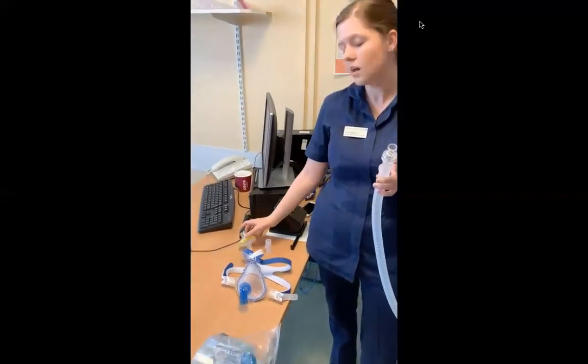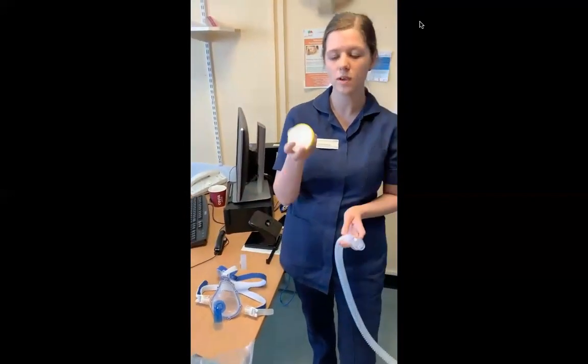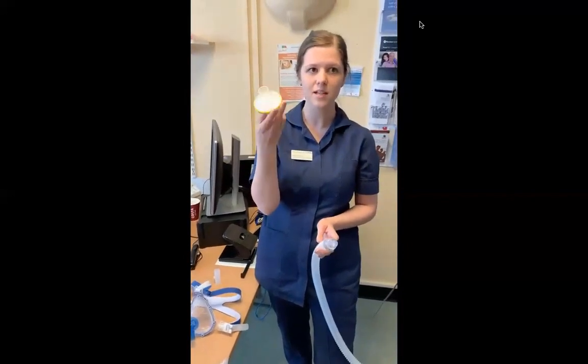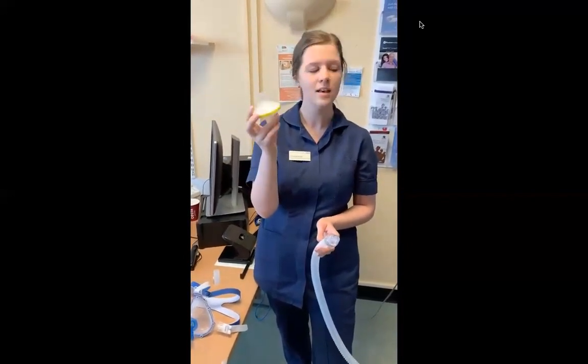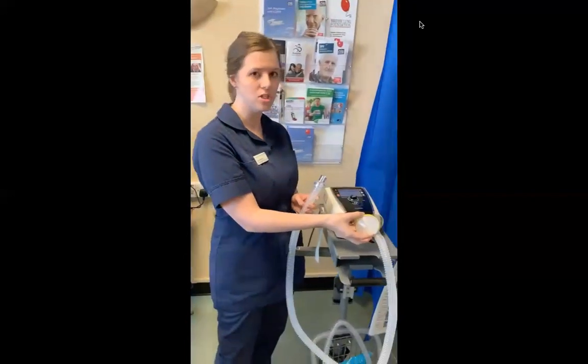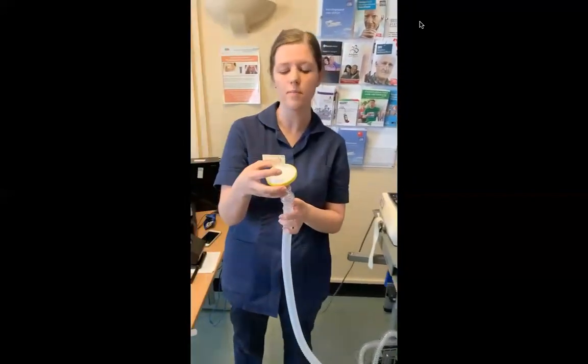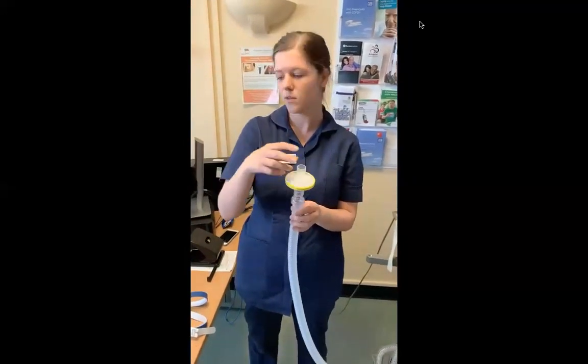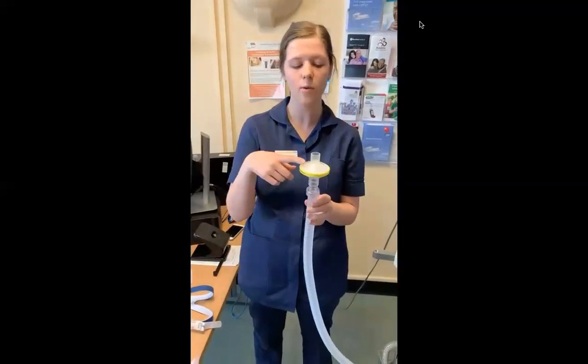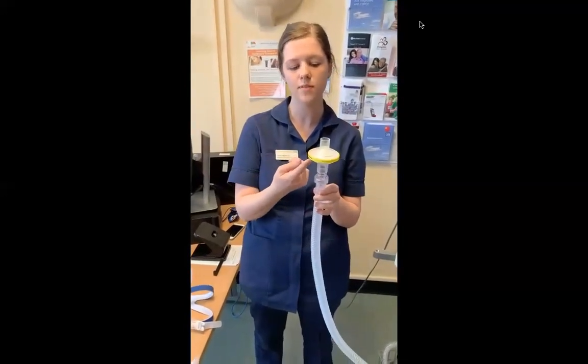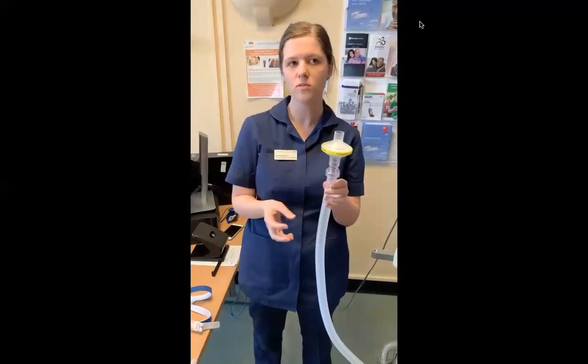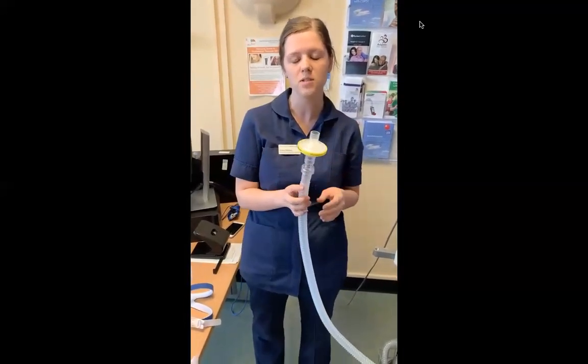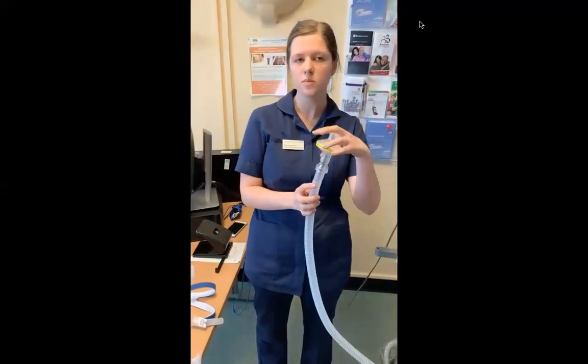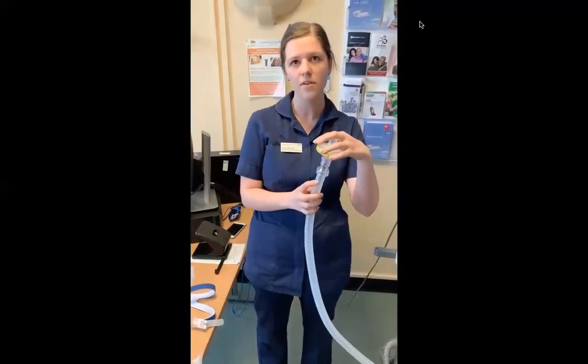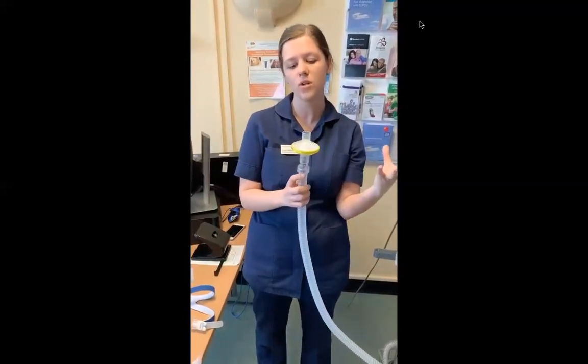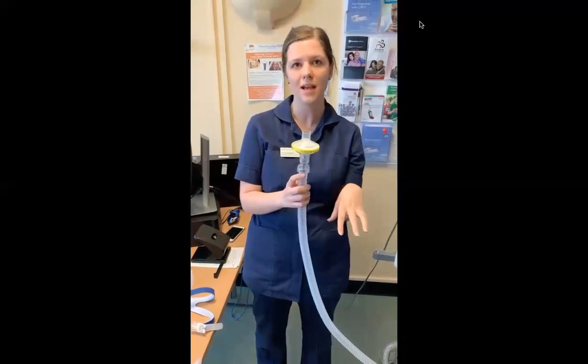In order to make it safer for you as well, we're also having the HME filter. This is a bacterial filter that filters out the air. Instead of having it normally here at the machine, it's now being placed above the exhalation valve. The reason for this is when the patient breathes out, it's going to go through the HME filter, clean the air, and then filter out of the exhalation valve and into the atmosphere. We can't say this is 100% going to remove all of the COVID. However, it's good at cleaning, and hopefully it's going to help make it that bit cleaner for you.